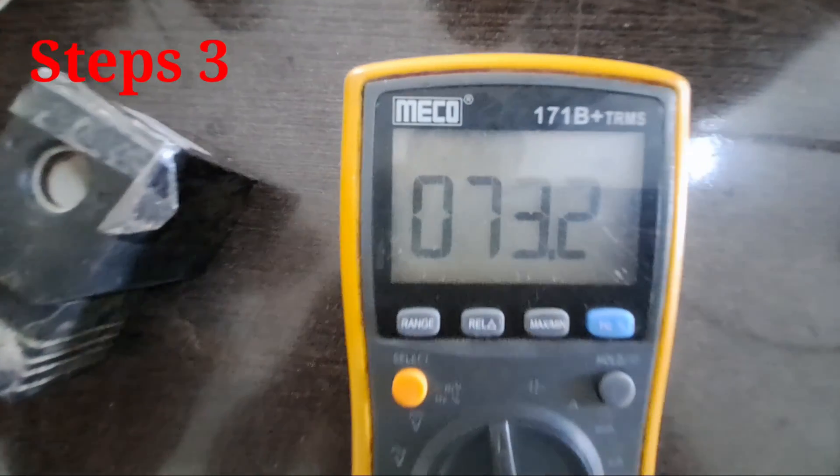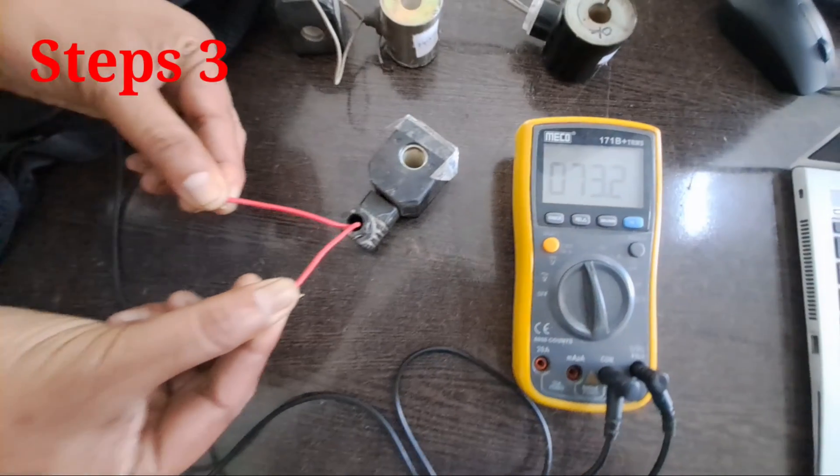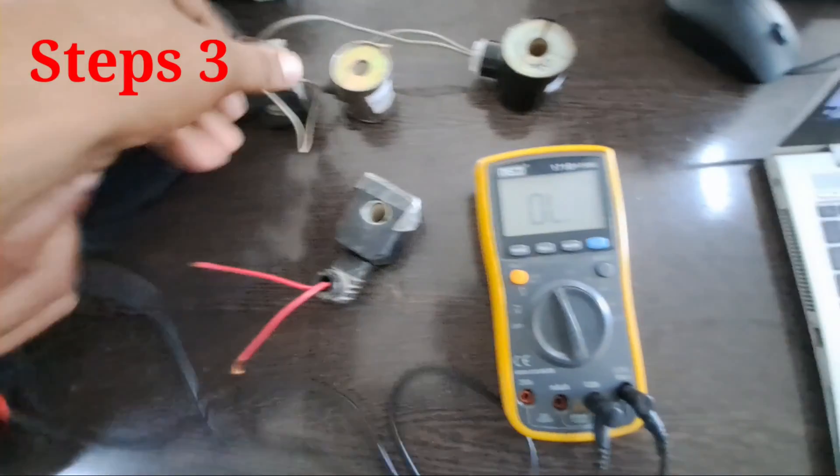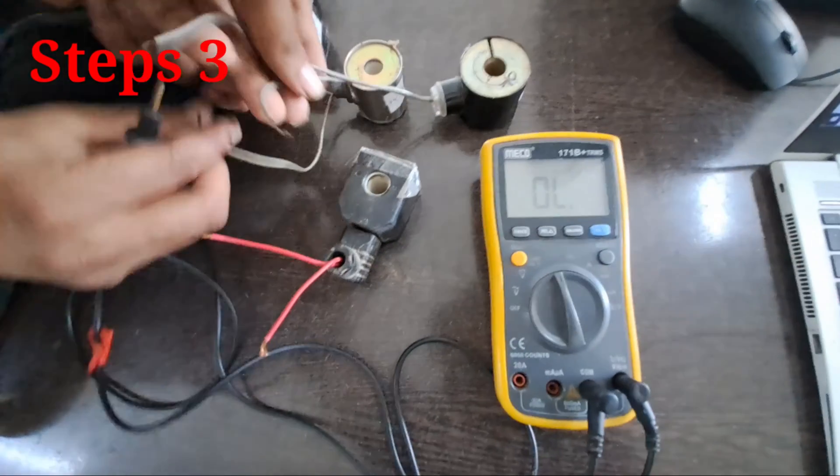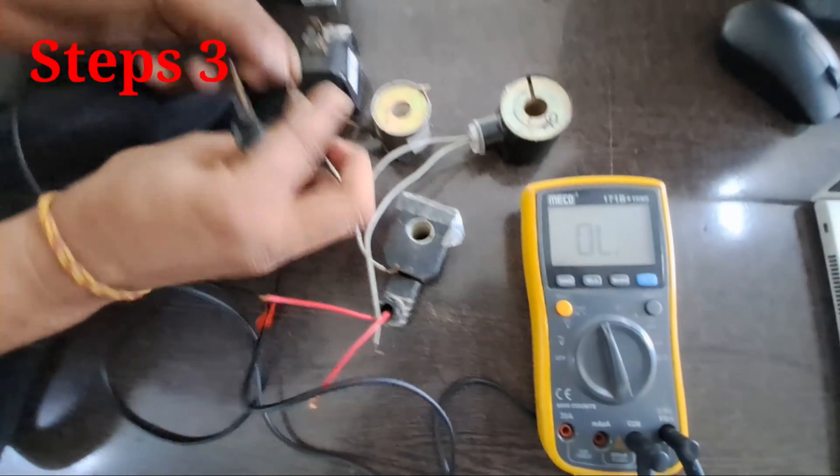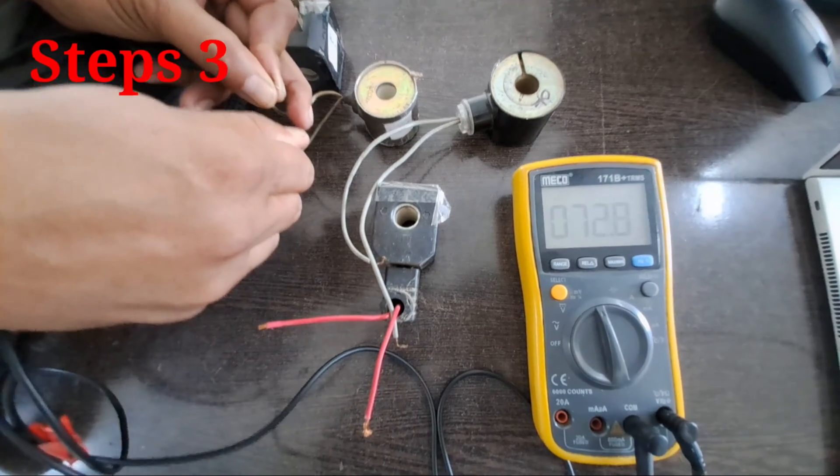Read the number on the multimeter. A functional solenoid coil normally has its resistance within a certain range. This range varies from manufacturer to manufacturer, but definitely not zero. If you have zero ohms, it means the coil is shorted.